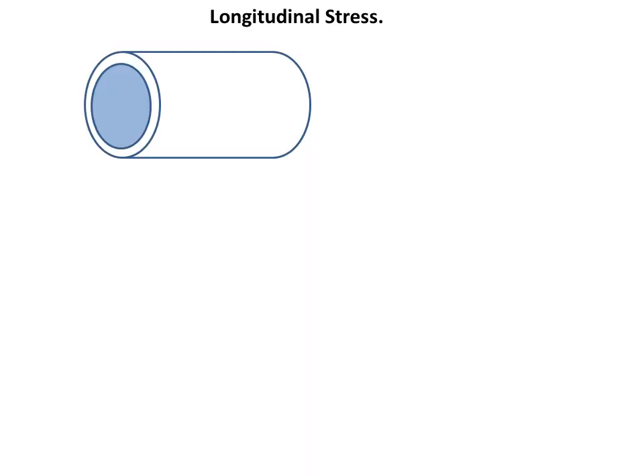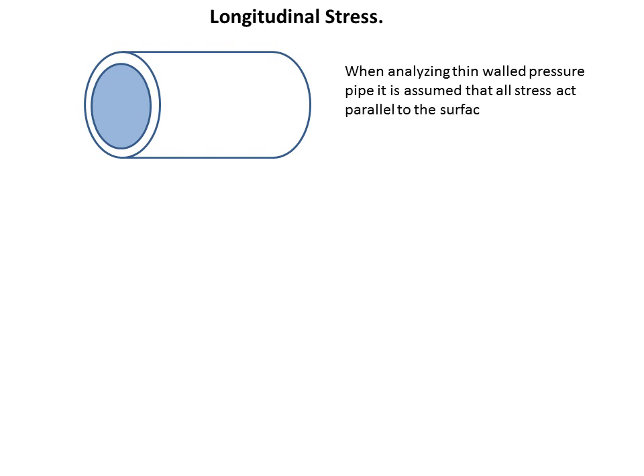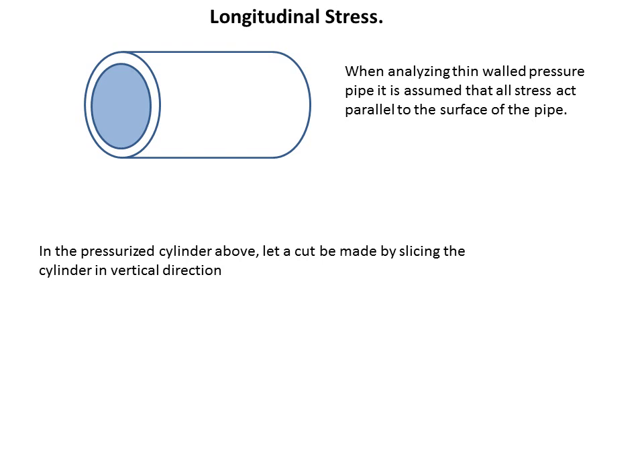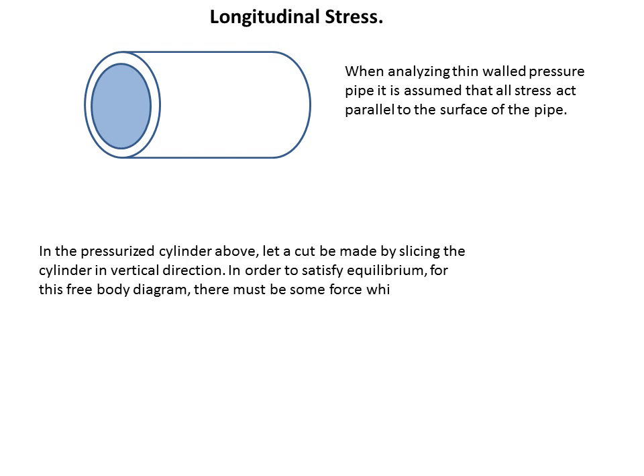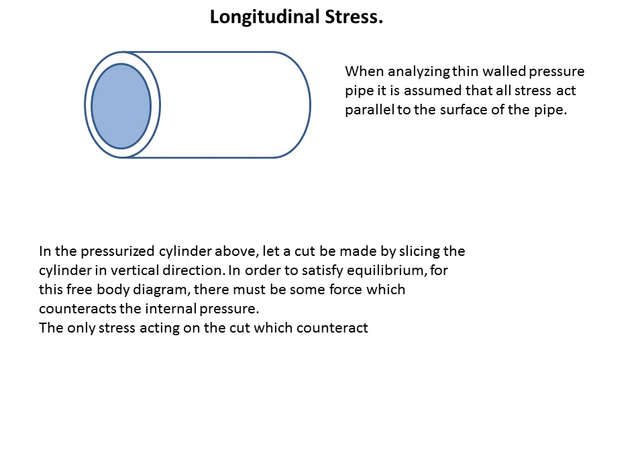We will start with the discussion on longitudinal stresses. When analyzing thin-walled pressure pipe, it is assumed that all stresses act parallel to the surface of the pipe. In the pressurized cylinder, let a cut be made by slicing the cylinder in the vertical direction. In order to satisfy equilibrium for this free-body diagram, there must be some force counteracting the internal pressure. The only stress acting on the cut which counteracts the internal pressure is the normal stress SL — the longitudinal stress.